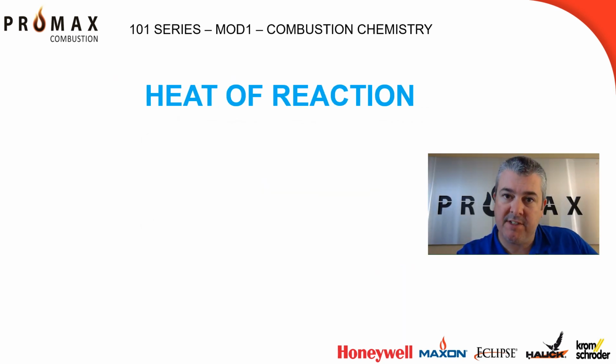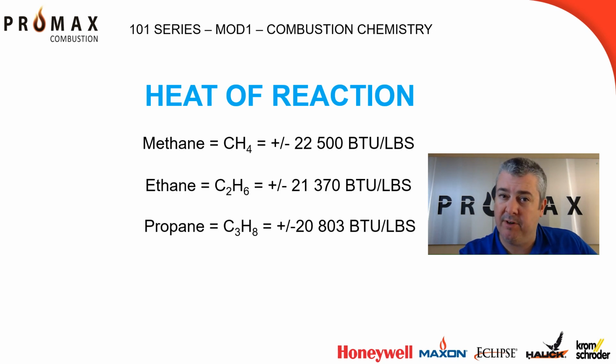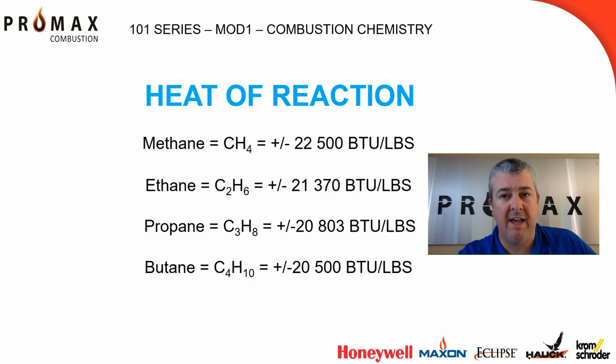The net difference in the heat released and the heat absorbed by the combustion process is called the heat of reaction for a given fuel. Interestingly, most hydrocarbons have very similar heat of reaction values. As you can see from the slide below, the hydrocarbons most used in industrial applications all yield about 20,000 BTUs per pound of fuel.